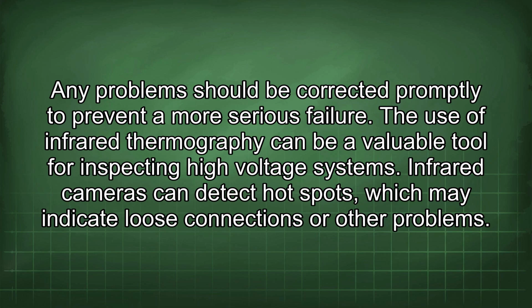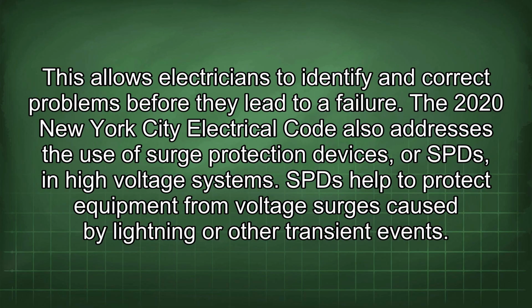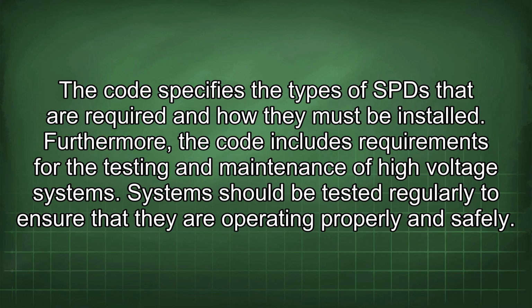The use of infrared thermography can be a valuable tool for inspecting high-voltage systems. Infrared cameras can detect hot spots, which may indicate loose connections or other problems. This allows electricians to identify and correct problems before they lead to a failure. The 2020 New York City Electrical Code also addresses the use of surge protection devices, or SPDs, in high-voltage systems. SPDs help to protect equipment from voltage surges caused by lightning or other transient events. The code specifies the types of SPD that are required and how they must be installed.